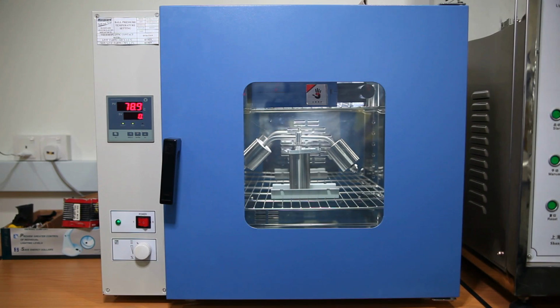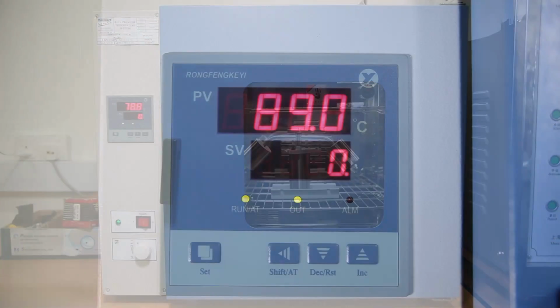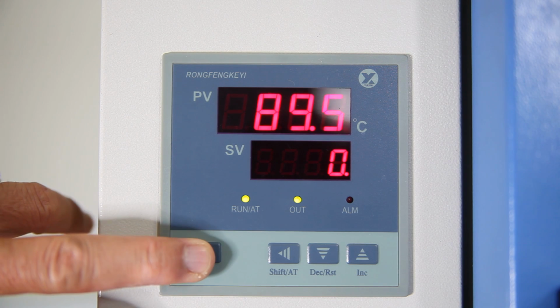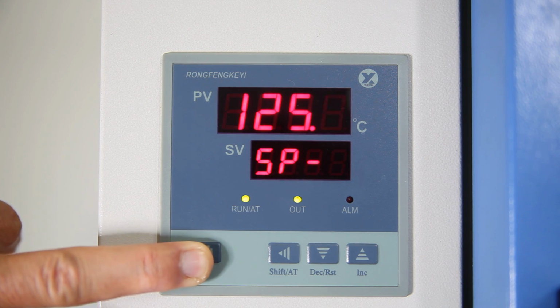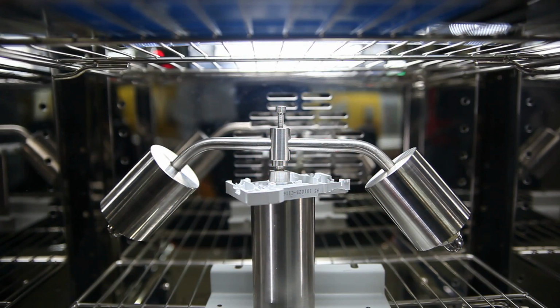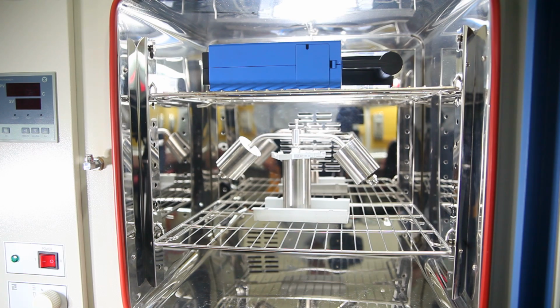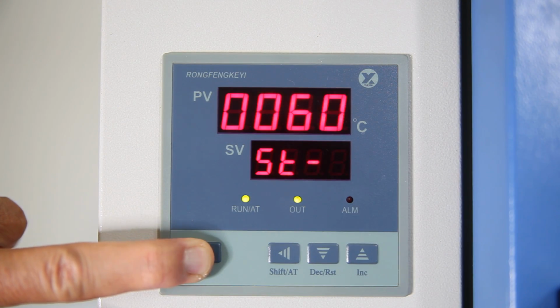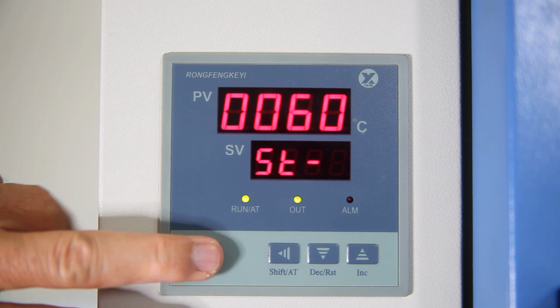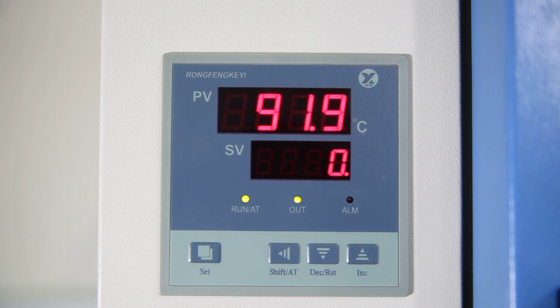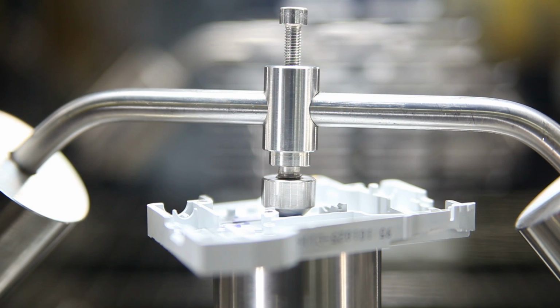Ball pressure test. The ball pressure tester is used to verify the capability of the thermoplastic parts retaining or touching current carrying parts to withstand the abnormal heat of excessive temperatures. It also helps to verify the heat resistance of insulating materials for use in all electrical wiring accessories, appliances, and switchgear housing, etc., for operating at above room temperature.